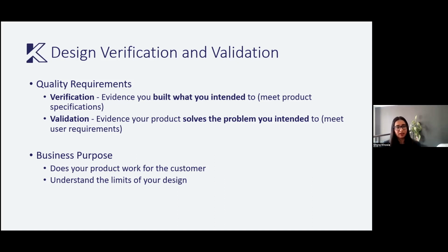On the flip side, validation is: did you actually solve the clinical need that you were trying to solve? So does that wavelength actually image the tissue and get you the right images for your clinician to make a diagnosis on, if that's what your intended use is? So what you're doing here is defining test protocols for how to do this, and then writing reports that show that you meet your product requirements.